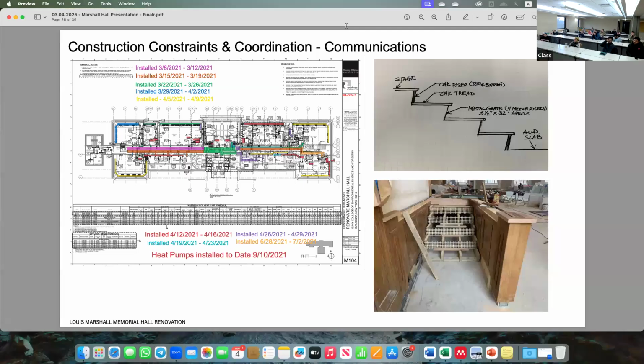There's an open plenum underneath the stage with about a 72-inch by 40-inch piece of ductwork that draws air underneath the stage, and there was one 32 by 40 vent in the front of the stage. They were supposed to open up a bunch of grills hidden in the front, matching some of the historic detailing. But when they opened it up, there were structural members we didn't know about that blocked the top half of the entire stage.